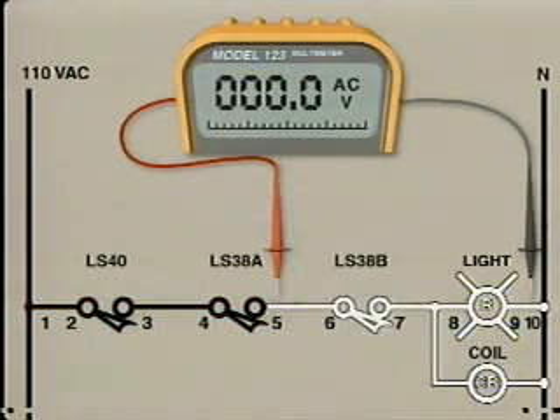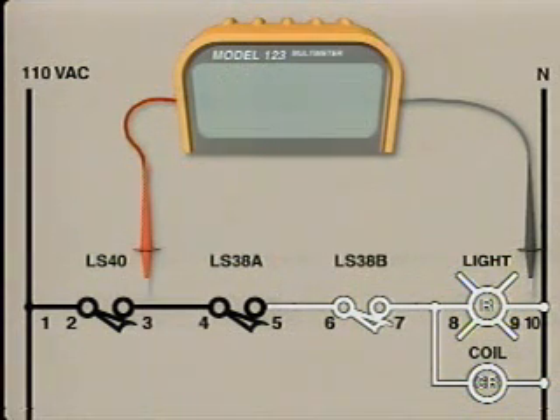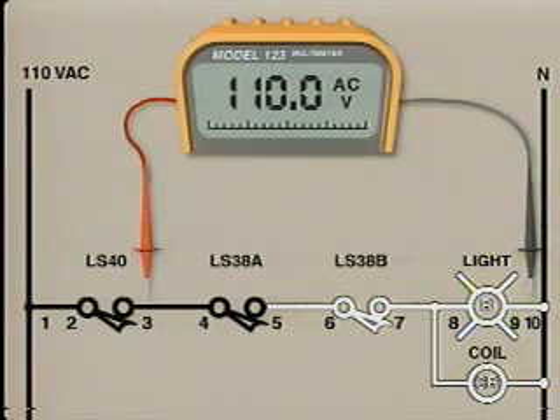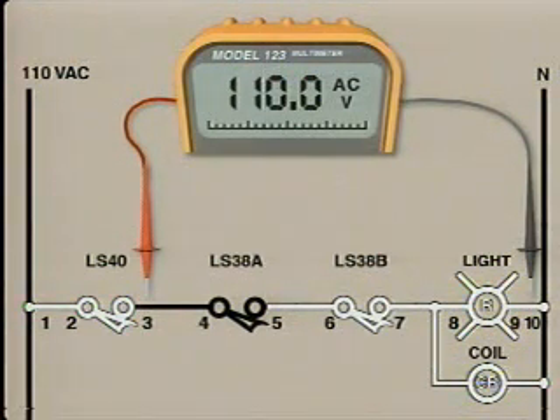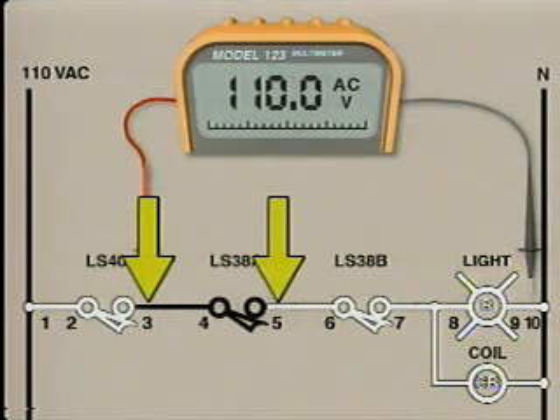It also means that none of the components between test point 5 and test point 10 can be causing this startup problem. The electrician half-splits the circuit again by measuring the voltage at test point 3. This test will check the path from test point 1 to test point 3. Here, the voltmeter indicates full line voltage. This tells him that the voltage at test point 1 is also present at test point 3. This means that this portion of the circuit can be eliminated from consideration as containing the source of the problem. So the problem must be an open between test point 3 and test point 5.